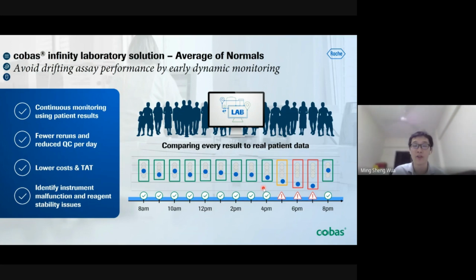This is where the average of normal will help you monitor the instrument's performance. By using the average patient data, we are able to see whether there is any drift happening. If, let's say, at about 5 p.m. there is a drift based on the patient average, then you'll be able to see that there is an issue with the instruments or with the reagents. Then you can do troubleshooting. This will help you identify any issues earlier. Let me just show you a video on this.